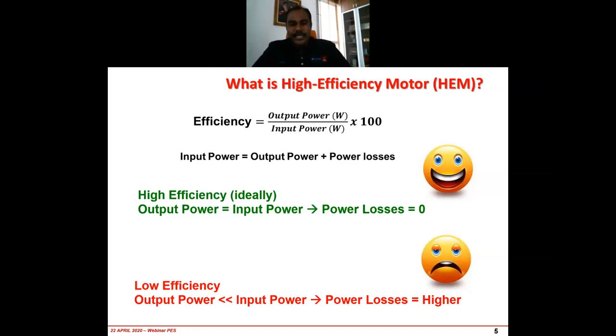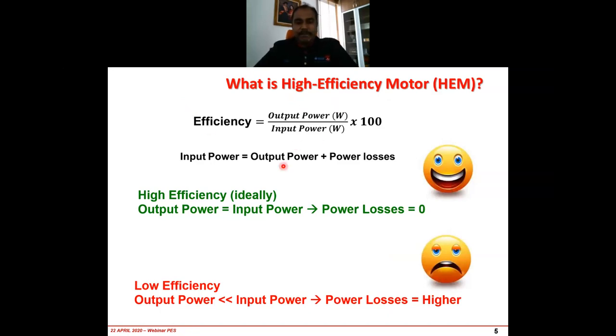When you talk about high efficiency motors, obviously from the word efficiency, that means that particular motor will have lesser losses. If you look quickly at the equation for efficiency, it is the output power over the input power. Output power for a motor is mechanical power, and input power is electrical power, right? So the input power is the output power, which is mechanical power, plus the losses. So if we are talking about high efficiency, we are talking about zero losses, which is the ideal case, or the minimum losses possible, so that you achieve high efficiency. If you have high losses, then you have low efficiency. This is something that we know.